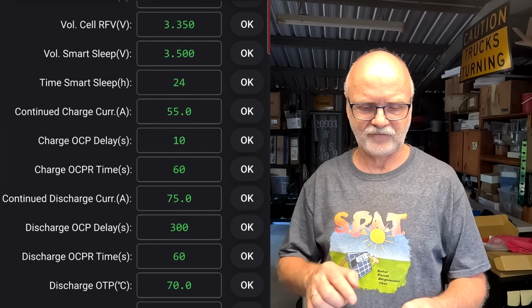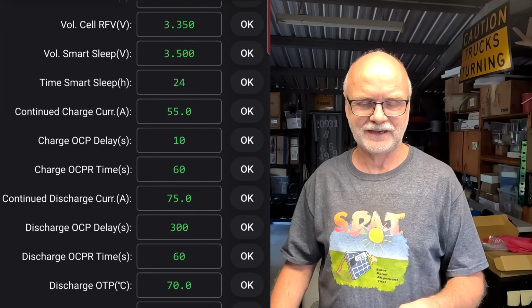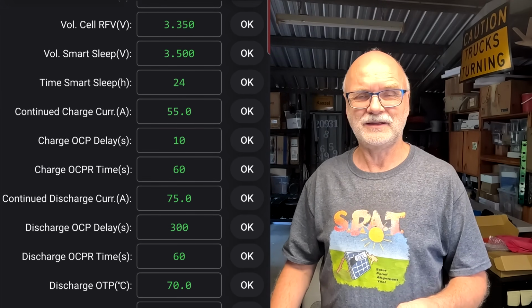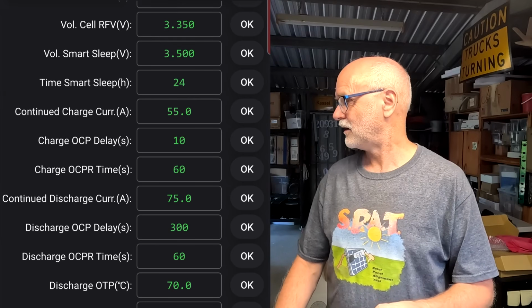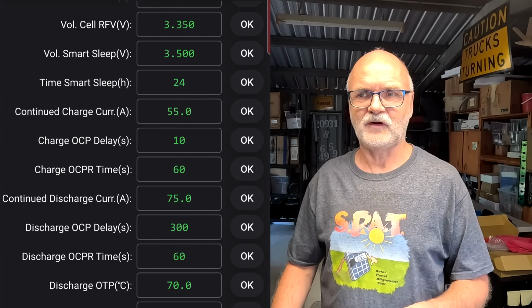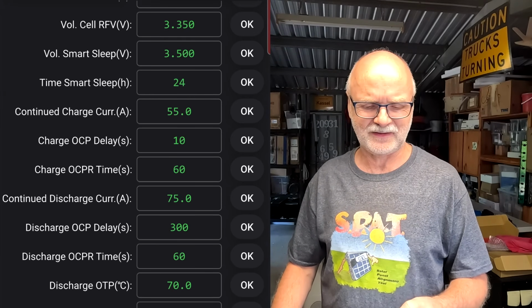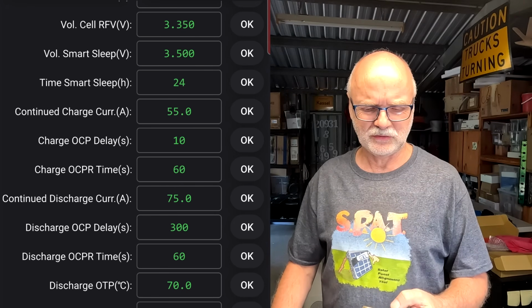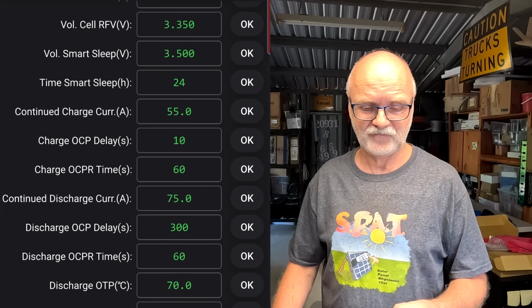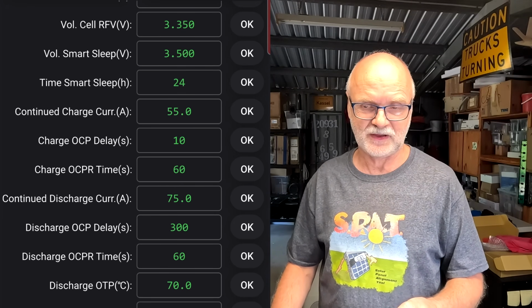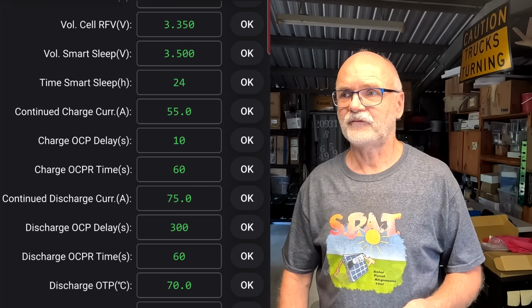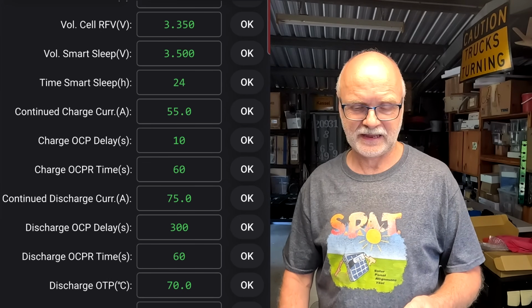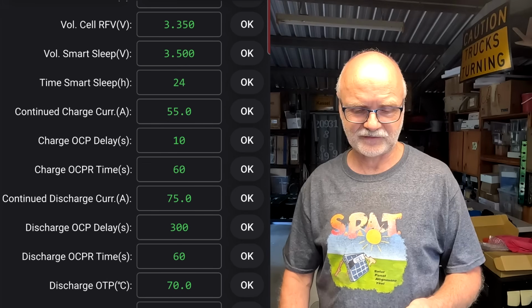We've got a 55 amp continued charge current limit. This is a 100 ampere hour battery. Yeah, probably leave this on 55 amps, I'm not expecting these high currents anyway. Continued discharge current 75 amps, which is fine. And here we've got 100 amps and 100 amps as hard limits for the protection.